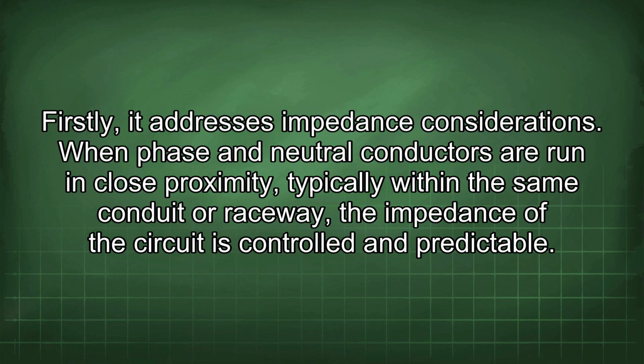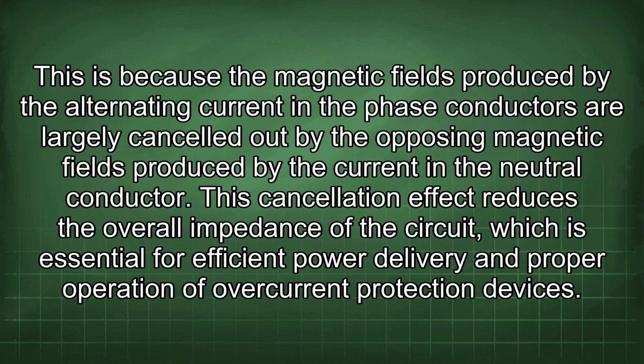Firstly, it addresses impedance considerations. When phase and neutral conductors are run in close proximity, typically within the same conduit or raceway, the impedance of the circuit is controlled and predictable. This is because the magnetic fields produced by the alternating current in the phase conductors are largely cancelled out by the opposing magnetic fields produced by the current in the neutral conductor.